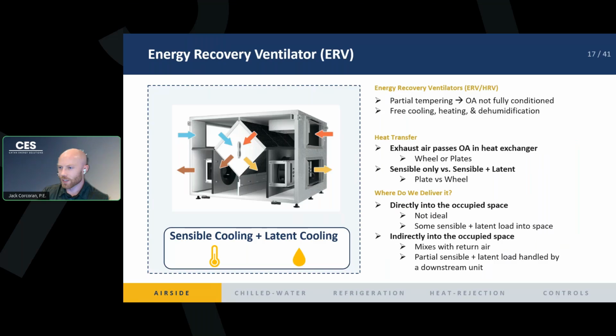Now we can talk about the ERVs, right? Our energy recovery ventilators. These partially temper, right? Looking at it a little bit closer, you can see these arrows. If you follow the blue on the left side, it goes into the unit. That's our outside air. It passes through that box, which is the heat exchanger, and it essentially captures the heat from the exhaust air, which is the orange coming in from the top right, so that you can deliver a more neutral temperature into the space, right? Our sensible cooling and latent cooling is like a yellow color here. It's not blue, but it's not the hot red that we had with just the fan. It's somewhere in between. But again, as we said a little bit earlier, it's free, right?